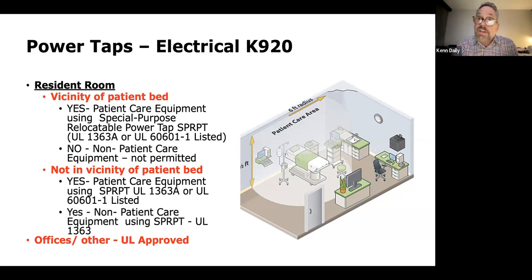But there is no path to compliance for non patient care equipment. So resident items like lamps and chargers and TV and anything that's theirs, residents', is not going to qualify for any kind of power strip of any level. It's only for PCRE for temporary times that you could use a PCRE and a power strip that's appropriately certified. Not in the vicinity of the patient bed. Most of your rooms aren't even big enough to do this, so it's not really applicable.